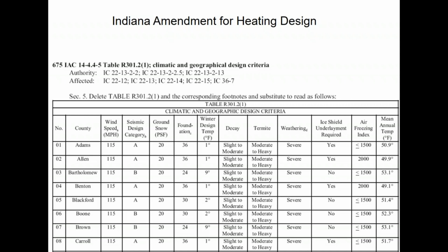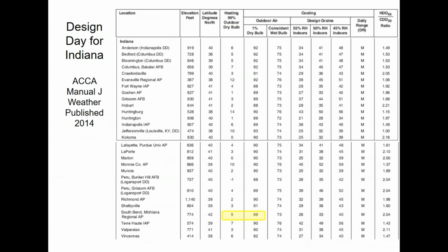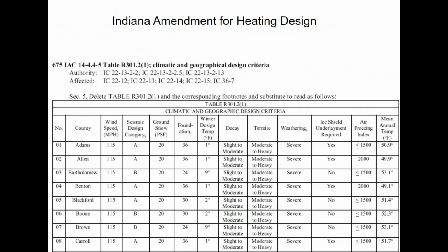But you can just see that column where it says winter design temp. All of the counties in the northwestern portion of Indiana, right? So Lake, the examples I gave before, if you were doing a job in Hobart or South Bend, right? So if we go back to South Bend, 5 degrees, the state amendment is 1 degree. So even though the load calc is supposed to be based on 5, in Indiana for South Bend, you would make it 1 degree instead. So you're getting a little bit of extra buffer there.